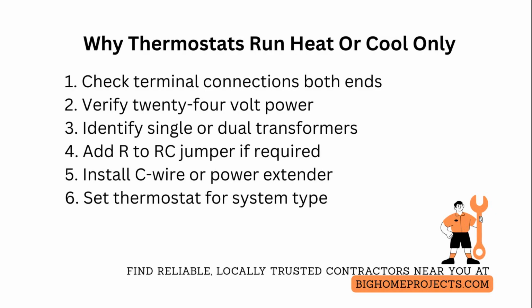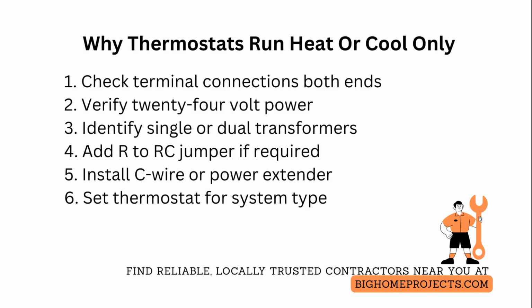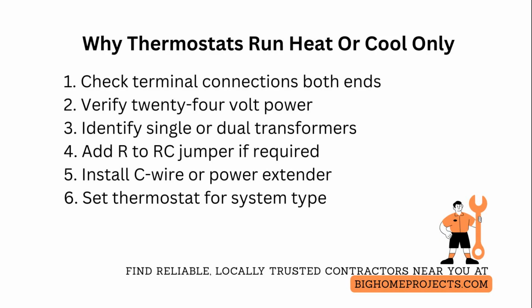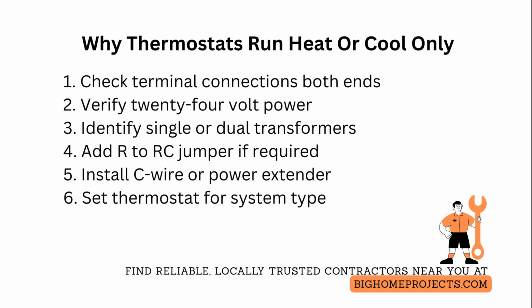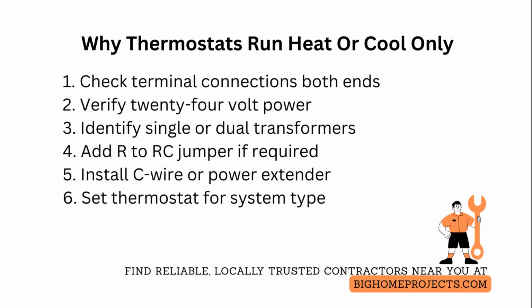Use a multimeter to verify 24-volt control power between the red and common terminals and to check for voltage when calling for cooling. Next, verify whether the system uses a single transformer for both heating and cooling or separate transformers. If there are separate transformers, the cooling circuit may require a jumper or a thermostat designed for two transformer systems. Otherwise, you will need to install an isolation relay or a thermostat with dual transformer support.